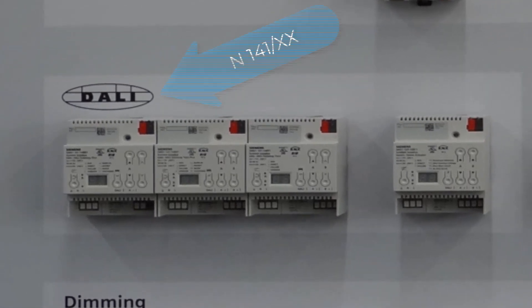Let's now turn to the subject of lighting control with DALI. With the DALI Gateways Plus, Twin, and Twin Plus, Siemens offers a coordinated device portfolio. These differ in terms of the number of DALI channels, functions and properties, and support for all DALI sensors such as the DALI pushbutton interface. The DALI family was extended by a DALI switch dim actuator offering two DALI channels; via these channels, up to 20 DALI ECGs can be controlled via DALI broadcast.